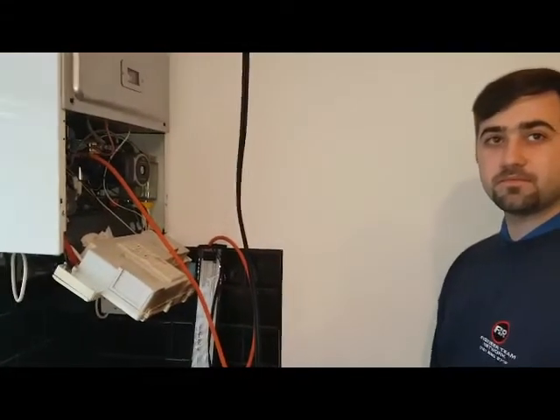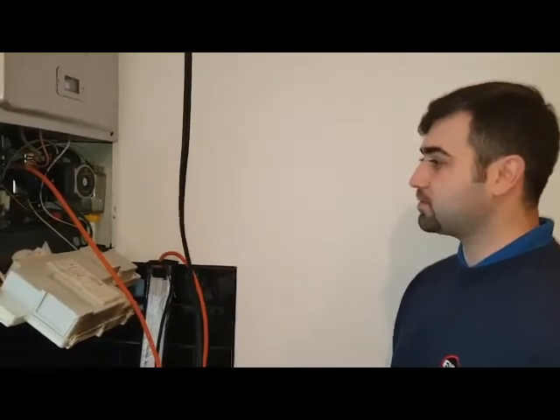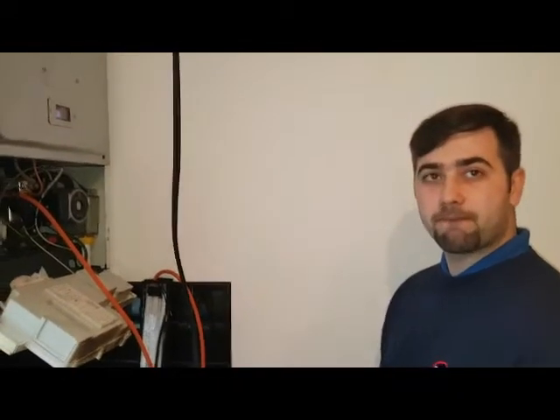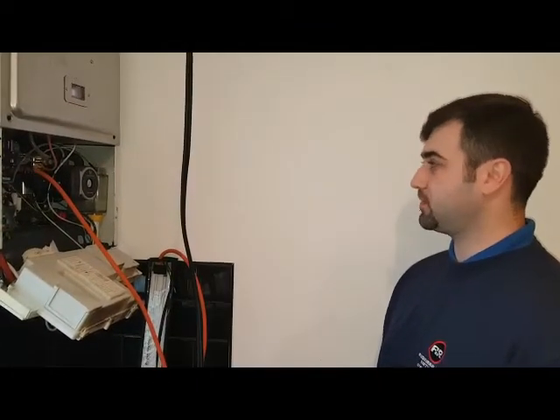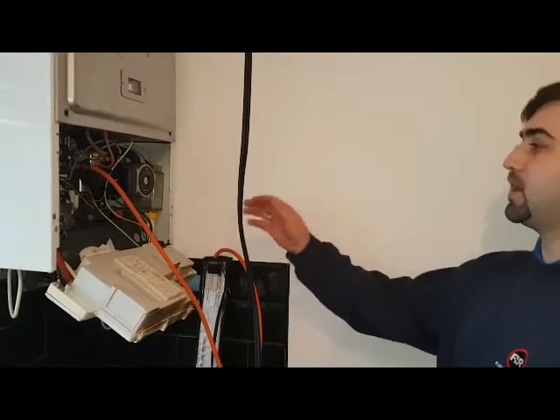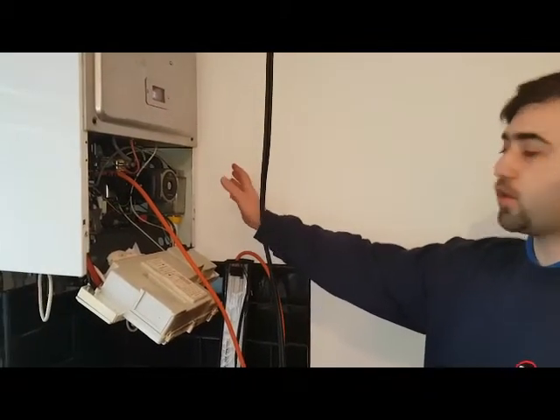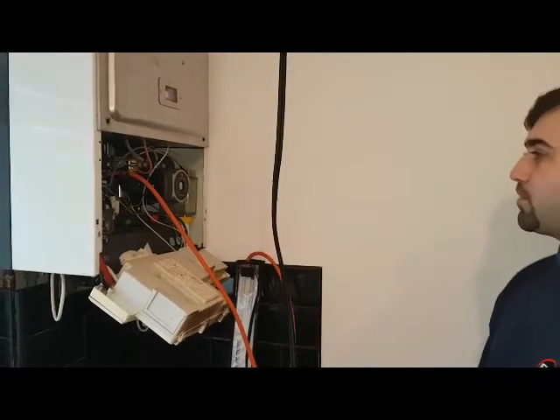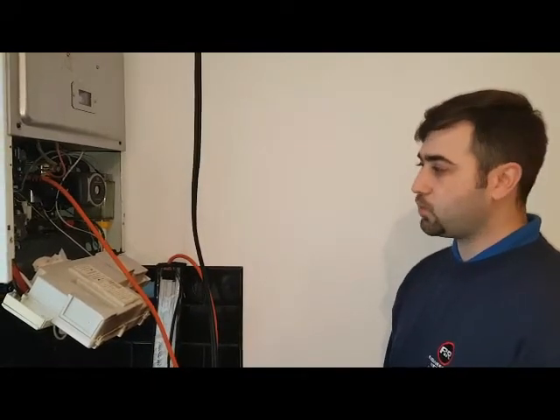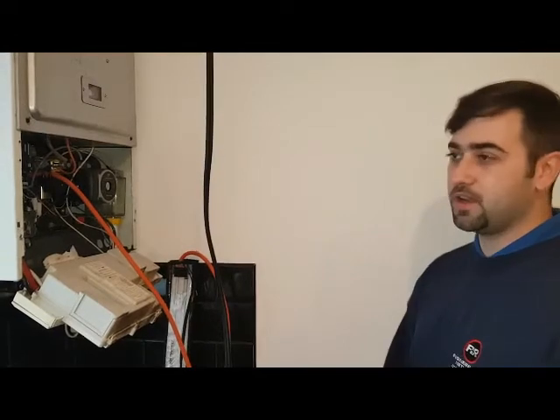You're going in a real short space of time. Just tell me some of the jobs you've done. Yeah, I've been doing some repairs, some boilers. You've done an Ideal Exclusive — the blocked expansion vessel pipe? Oh yeah, basically there was an expansion pipe blocked so I had to take it out, but to be able to do that I had to remove basically most of the parts on the boiler. I got it all out, put everything back and the boiler started working — and I couldn't believe I did that.